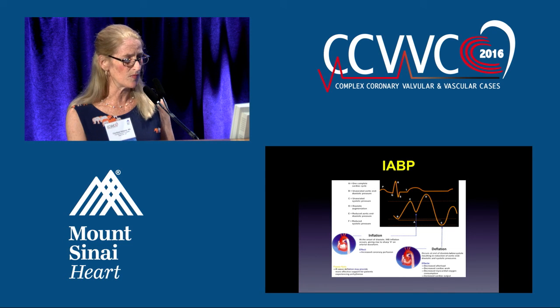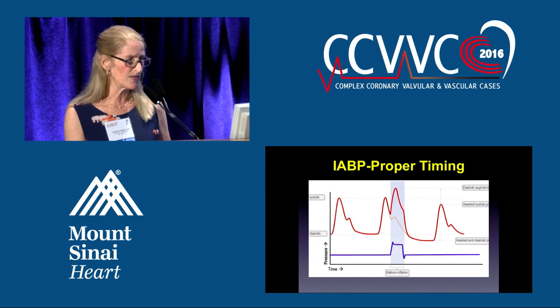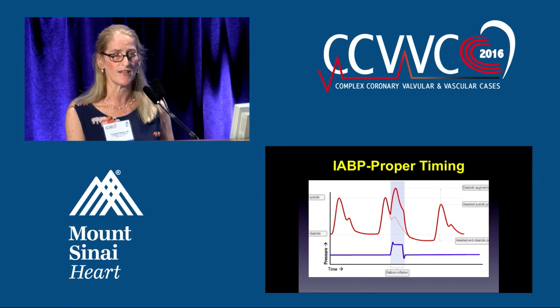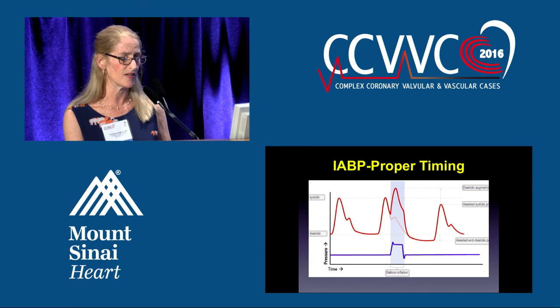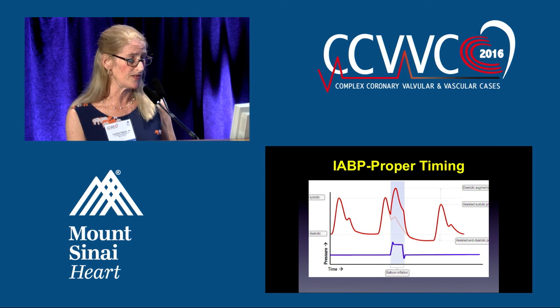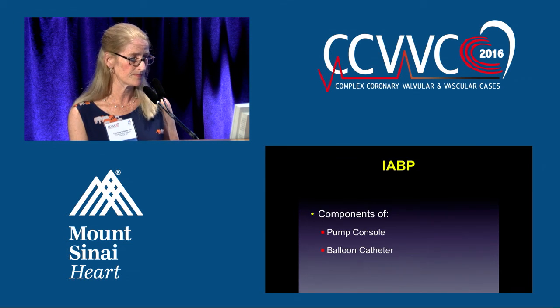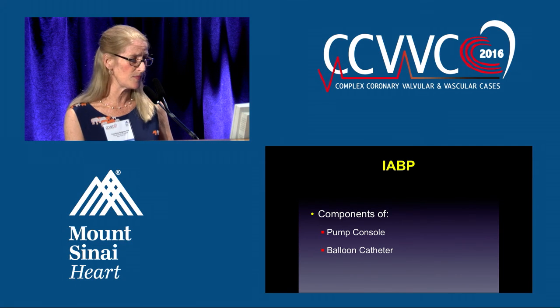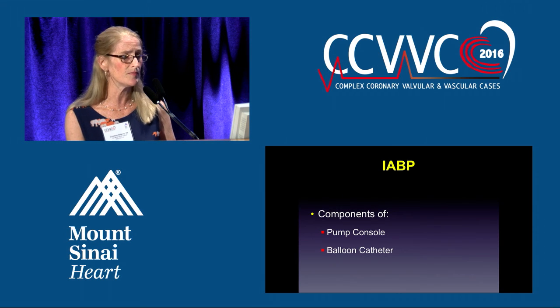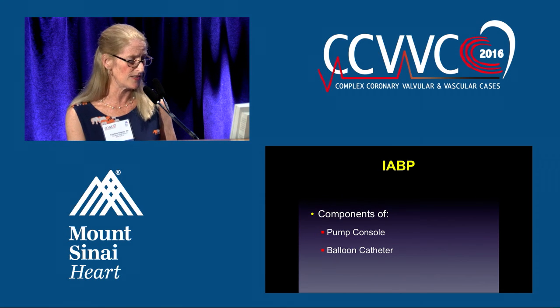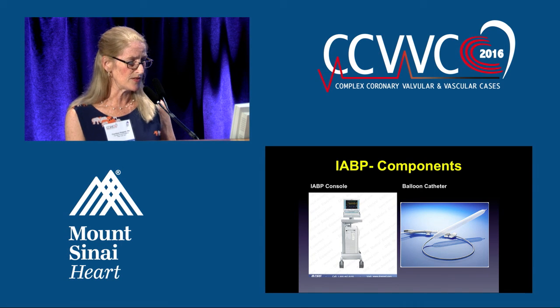This is just a reminder of that waveform we're all so familiar with, just to remind you that the timing has to be pretty precise. If the timing is off, at best, you're not going to help the patient, and at worst, you can actually do more harm than good. The components of the IABP are very simple. We have the pump console that contains the helium that inflates the balloon, and the catheter itself. On the left, of course, is the console. On the right is the balloon.